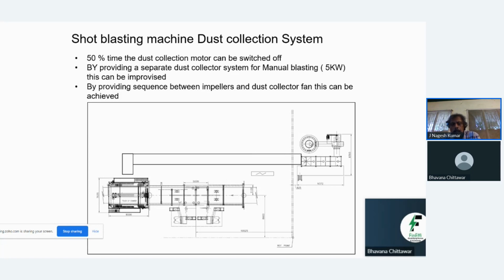So rather than that, if you come back into the process, rather than doing all this activity around the blower, you come through this duct and see why this fan is required at all. From that why, you start the question. Then you find where exactly the blower has to act when the dust is coming out. So when you address these questions, then you find there's a 50% saving potential in this blower.